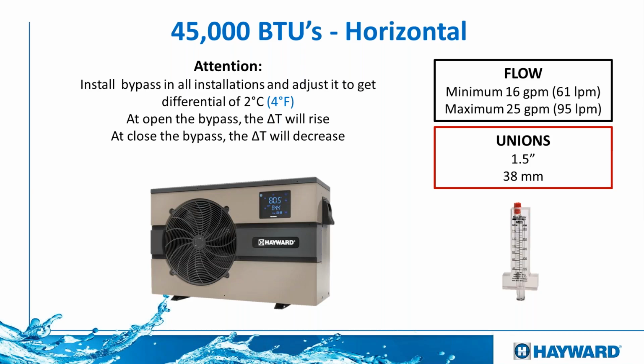And something to keep in mind with these units, they will always require a bypass, because the recommended flow rating for this is 16 to 25 gallons per minute. What that means is that we don't want to exceed the 25 GPM, because that is going to create too much pressure inside the unit. So it is always recommended to use an external bypass when installing this heat pump, and at the same time, always recommended with any type of heater to use a flow meter, because that's the only way that we can see exactly how many gallons per minute are going into the unit.